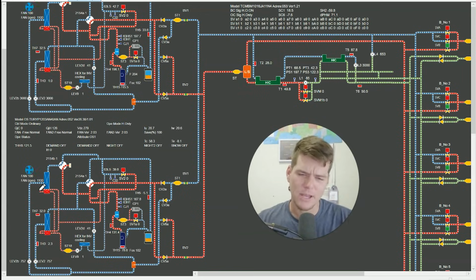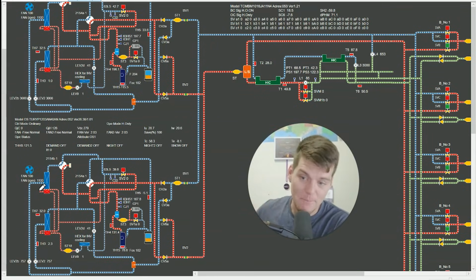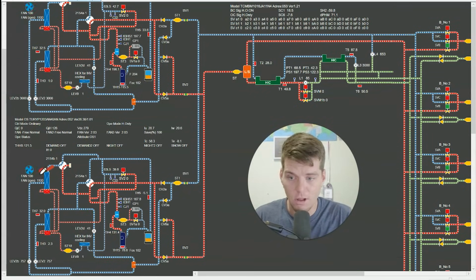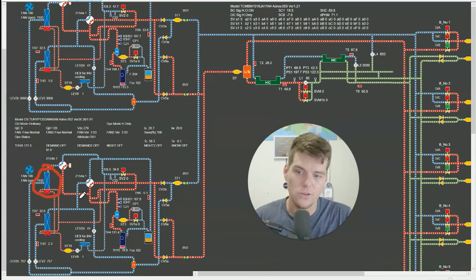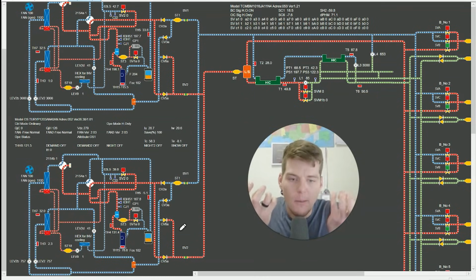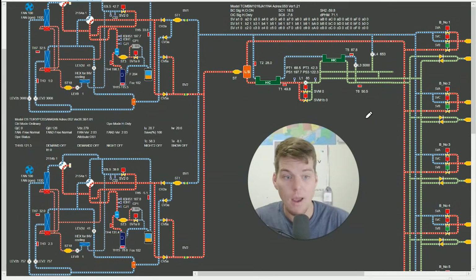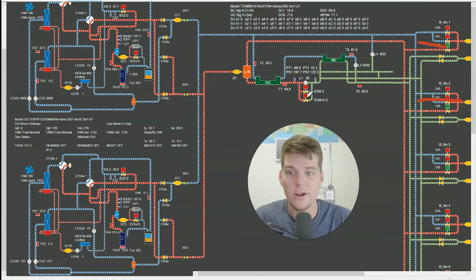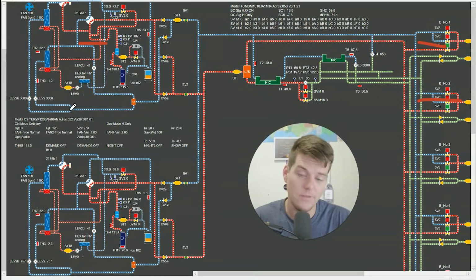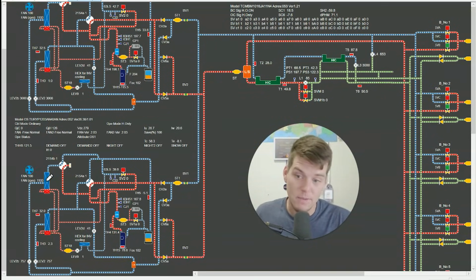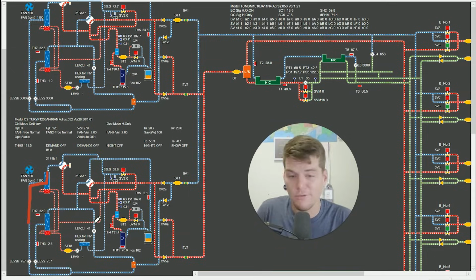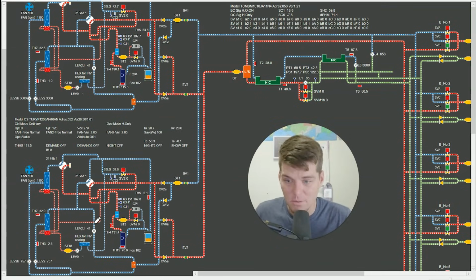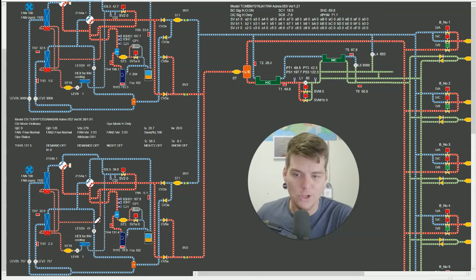So what's happening here? Explain a little bit more to me. So if that becomes a liquid receiver, we're stacking all of our liquid in the lower heat exchanger on this unit. Well, now we're sucking up charge like a sponge. Now I'm pulling refrigerant from all the indoor units over here. I'm pulling refrigerant from the unit to the left of here. I'm doing all of that naturally because, again, it's freezing cold over here and I'm stacking liquid. So I've stacked so much liquid in this lower heat exchanger that now maybe I've pulled 50% of the charge out of the system. It's not circulating through the system like it's supposed to. So it's stacking in the sub module.